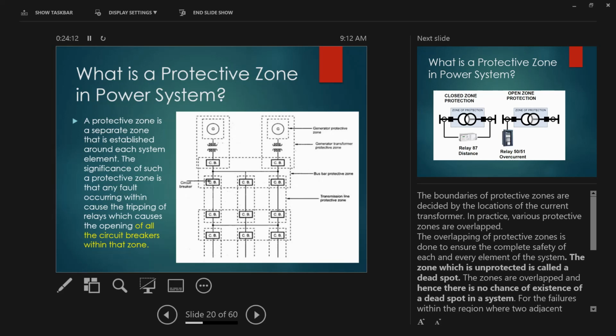So a protective zone is a separate zone that is established around each system. You can see those dotted lines. So it has its own protection. The significance of such a protective zone is that any fault occurring within it causes tripping of relays, which causes the opening of all the circuit breakers within the zone. Like for example, this busbar protective zone.